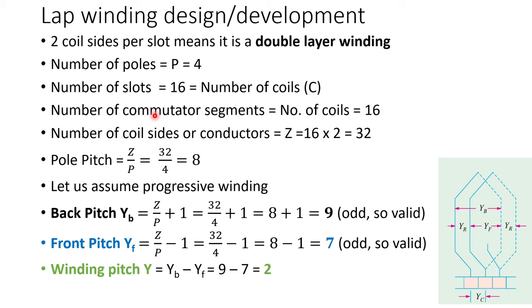We need to calculate the pole pitch. Total number of coil sides divided by the number of poles gives us the pole pitch equal to 8. Let us assume that it is a progressive winding. So back pitch would be given by Z/P plus 1, or pole pitch plus 1. If we assume retrogressive winding, the signs in back pitch and front pitch will get reversed. So back pitch would be equal to 9, and it is an odd number so it is valid for lap winding. Front pitch is Z/P minus 1, equal to 7, which is also odd so it is valid. Winding pitch would be back pitch minus front pitch for lap winding, so winding pitch YB minus YF would be equal to 2.